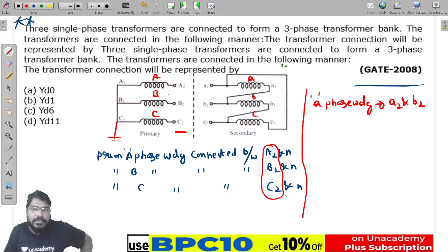Now in a similar way, what about the secondary windings here? The A phase winding is connected between A2 and A1, but A1 is connected to the B2 terminal. So the secondary A phase winding is connected between the A2 and B2 terminals. The B phase winding is connected between B2 and B1, and B1 is connected to the C2 outgoing terminal, so it is between B2 and C2. Next, the C phase winding is connected between the C2 and A2 terminals.